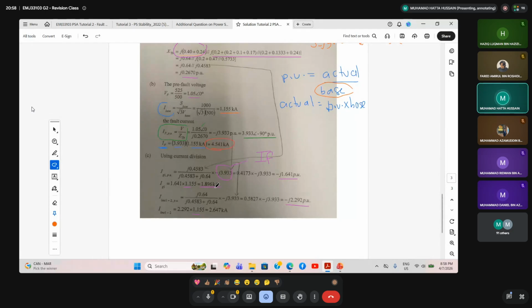Then again I have to do the same for I line from bus 1 to bus 2 in per unit, using the current divider again. I find the new value for the numerator, with the denominator staying the same, then multiply with the I fault to get a different answer - the current flow from bus 1 to bus 2, the transmission line.